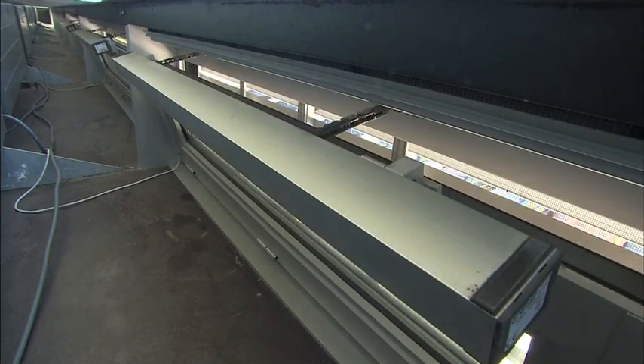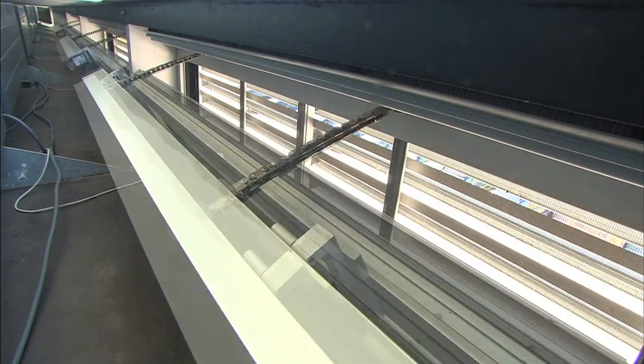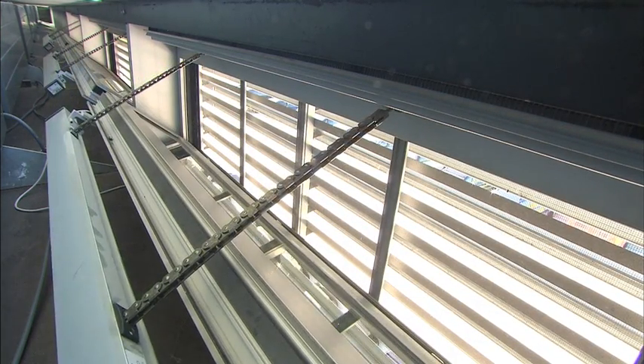The next key element of the healthy building concept is night cooling. Night cooling is an age-old technique which ensures a stable indoor environment through a combination of thermal mass and intensive ventilation. One characteristic of thermal mass is that it accumulates heat, or cold, and then gradually releases it.